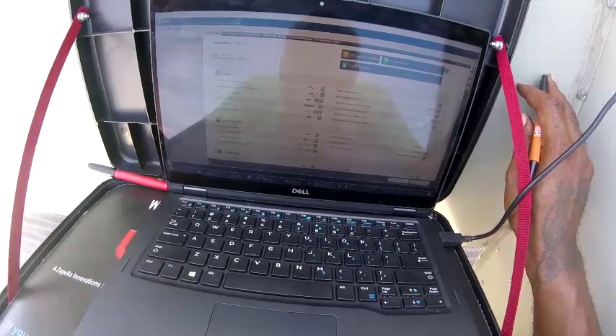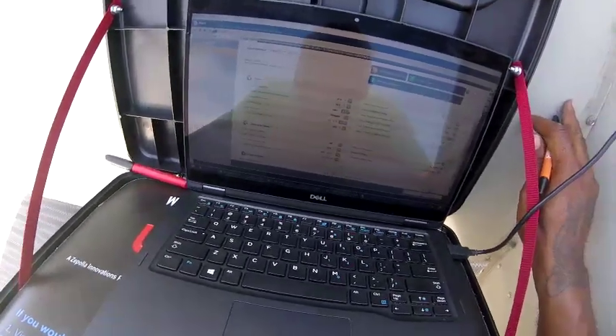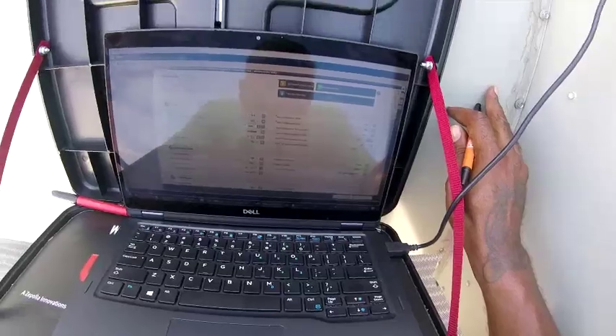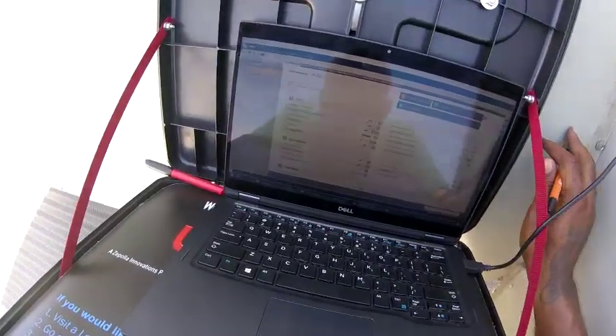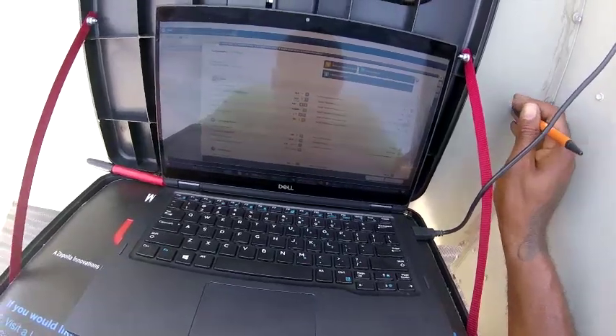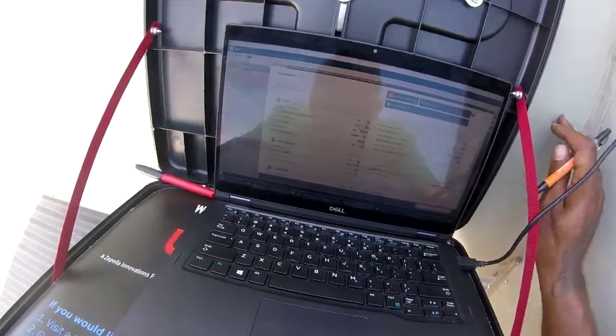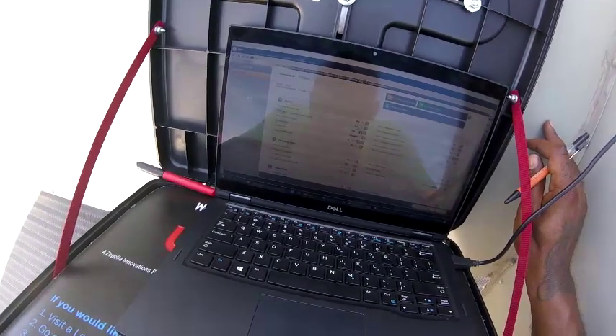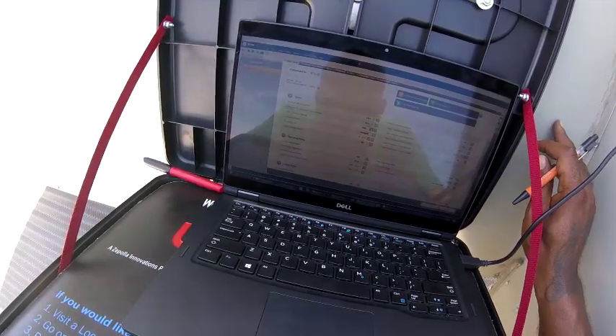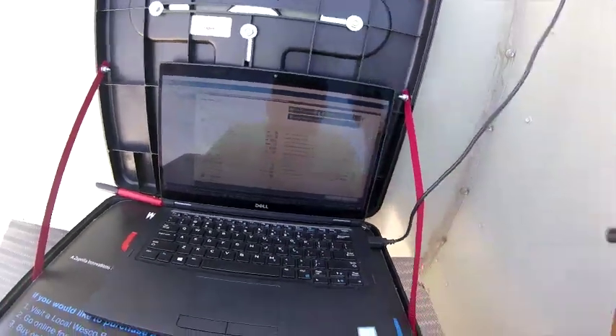So long as it doesn't go out on alarm since I hooked that switch back up, we should be good to go on this. But I'm gonna do my due diligence and monitor for a while and see what we got. The last time, when I hooked that fan proofing switch up, it went in alarm right away. But now it doesn't seem to be going in alarm.